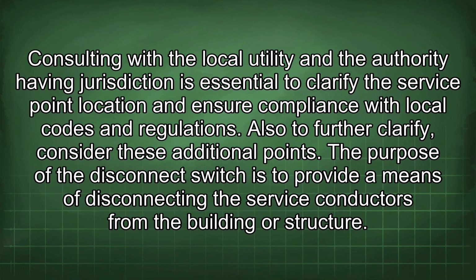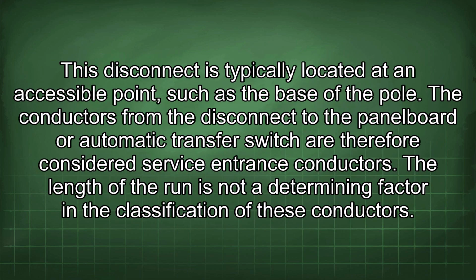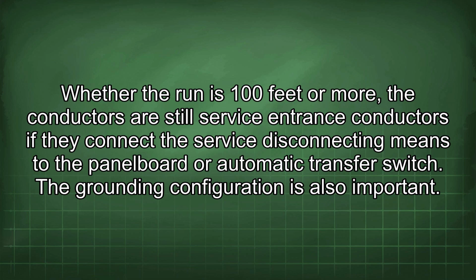Also, to further clarify, consider these additional points. The purpose of the disconnect switch is to provide a means of disconnecting the service conductors from the building or structure. This disconnect is typically located at an accessible point, such as the base of the pole. The conductors from the disconnect to the panel board or automatic transfer switch are therefore considered service entrance conductors. The length of the run is not a determining factor in the classification of these conductors. Whether the run is 100 feet or more, the conductors are still service entrance conductors if they connect the service disconnecting means to the panel board or automatic transfer switch.